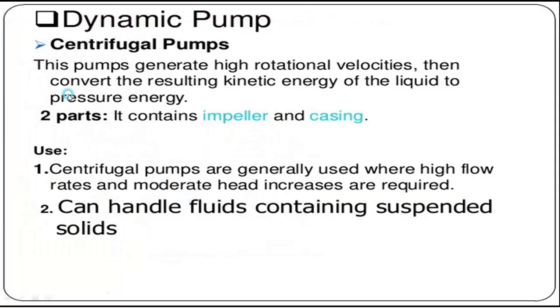Now the dynamic pump. In dynamic pumps we have the centrifugal pump. This pump generates, very important, high rotational velocities, then converts the resulting kinetic energy of the liquid to pressure energy. You spin the water a lot.